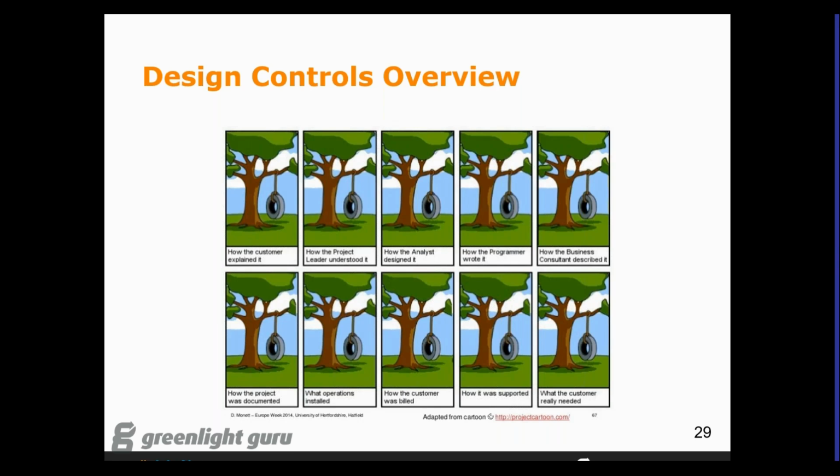That exercise took over 1,000 hours of effort of trying to sift through all of the different inputs, outputs, and validation documents to pull it together into a cohesive document so that we had all of those things linked together in the risk file. The fact that this was after the fact and not fresh in everybody's mind makes it very difficult, if not impossible, to pull all this stuff together.